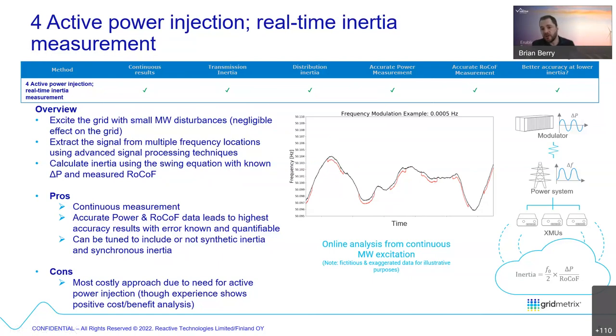We've got the power measured at the location of injection, so what we call a modulator. So we have a modulator creating this periodic injection, and we measure that very accurately. And we've got frequency measurements all around the grid. And we extract that from the noise, and that allows us to then calculate inertia essentially with a swing equation. So a very quick way of saying it is like applying the swing equation in the frequency domain, okay, with a periodic excitation. So that's what we do.